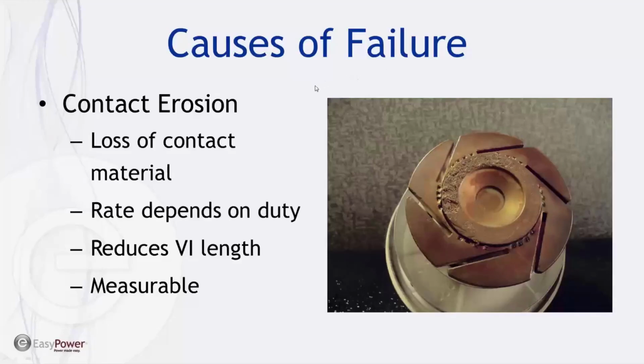However, fault currents drastically increase the amount of copper material that is removed from this surface. So it also depends on the application. What type of application it is can change the rate of erosion as well. Certain applications, like an arc furnace, where circuit breakers are operated like contactors, can cause the erosion to drastically increase. On those circuit breakers, vac interrupters are generally replaced every single year for that reason, because the contacts have eroded so much that the actual length of the VI is reduced.